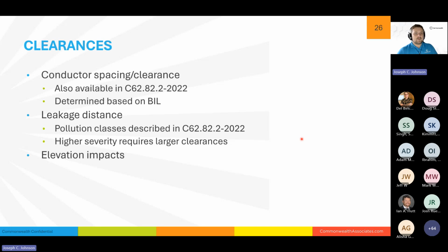And the last thing I wanted to cover was elevation impacts. So if you're building a substation up in the mountains, the air is thinner, and thinner air is less insulating. You can actually see a 20 to 25% decrease in the insulating properties of air. And so there is potential that you'll need to look into an even higher BIL or more arresters or a lower MCOV arrestor to make sure you're really protected, because it's not going to behave like it would at normal sea level.